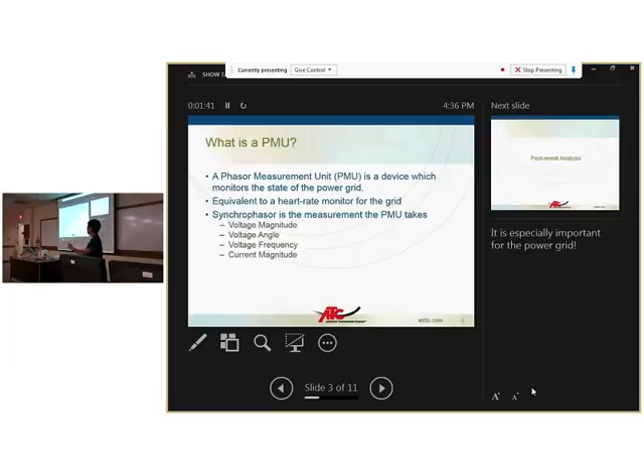Synchrophasor, you heard this word around everywhere within the presentation. It is the measurement the PMU takes - voltage magnitude, voltage angle, voltage frequency, and current magnitude. However, the current magnitude is not always there, it depends on the vendor. In the PMU that I've worked on, there were industrial PMUs, which consist of 3 phases rather than the 1 phase that Bogdan, Mike, Andy, and I are working on.